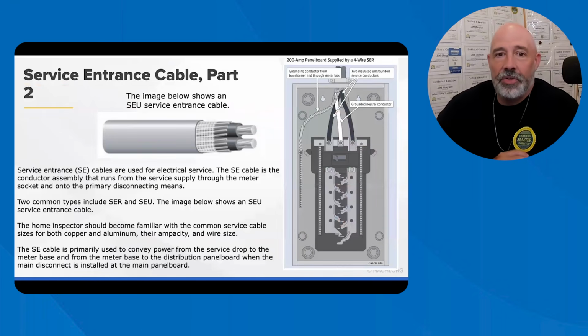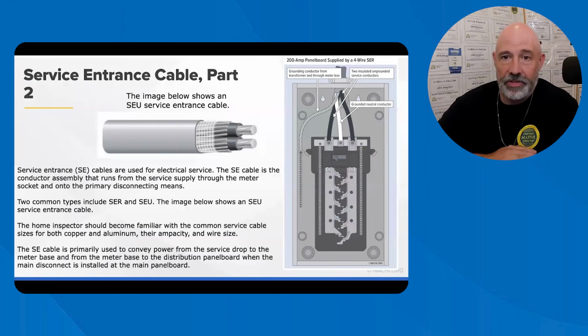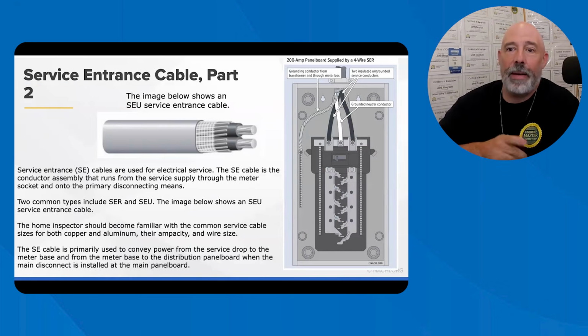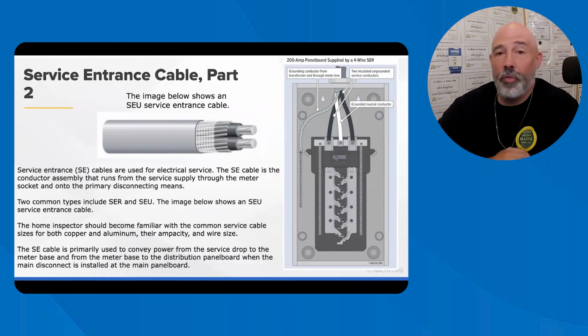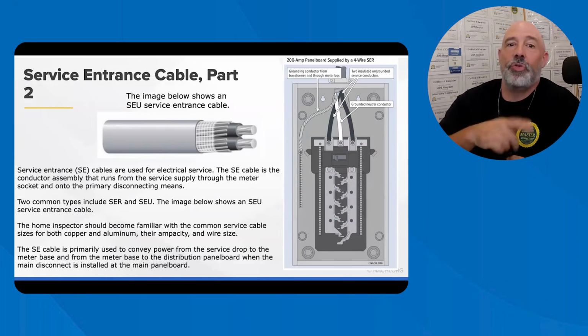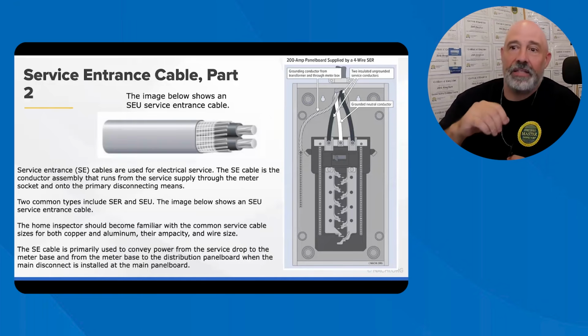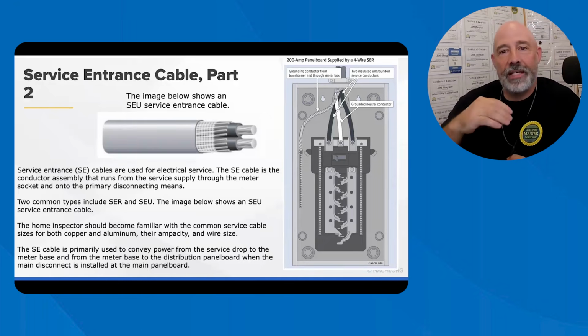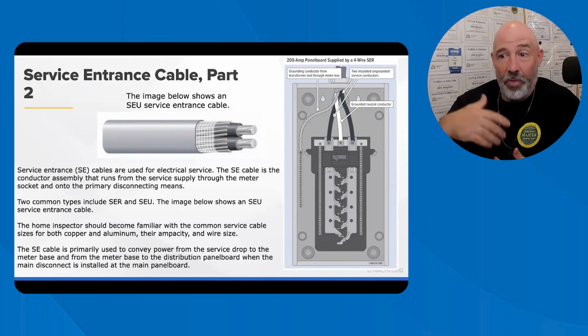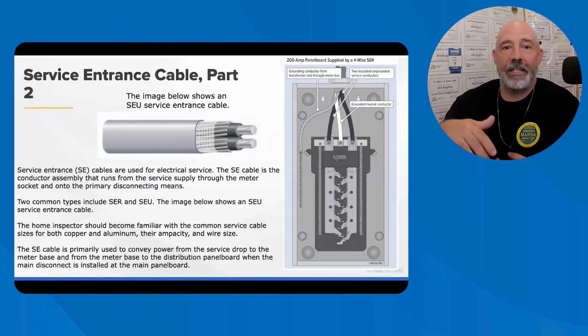Okay. The SEU is the unarmored service entrance three-wire cable with two conductors and a neutral. The SEU typically has a stranded neutral conductor that wraps around the cable to create an oval shape. The SEU cable has a neutral conductor but does not have a grounding conductor. Since neutral conductors and grounding conductors are connected at the same point, the service disconnect, SEU cables can only be used up to the service disconnect to avoid significant safety concerns.